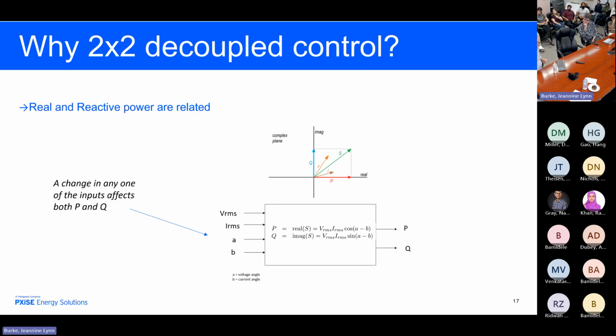You guys probably already know this, but why is a 2x2 controller needed? They're not used in the industry. We use very few single loop controls. You know, we use volt var control, we use frequency watt control. Those are not even real feedback control systems. Those are open loop scheduled systems using a proportional slope.